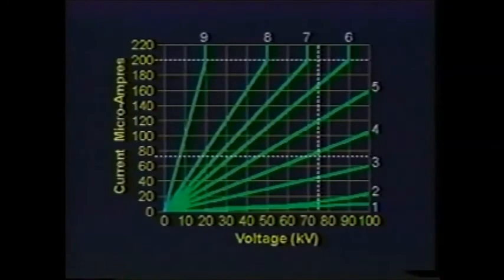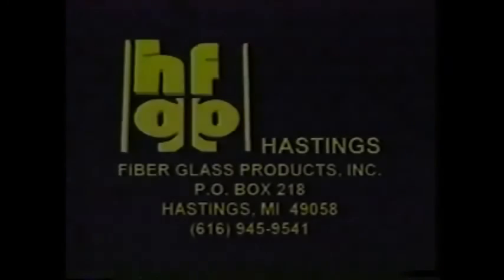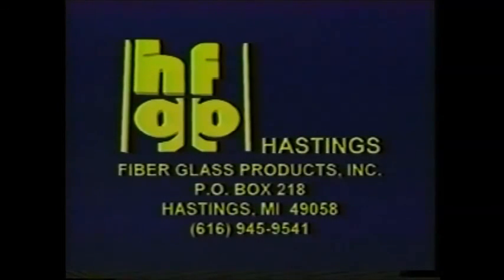This value will vary with the type and extent of contamination. To set 200 microamps as the accept reject level would come as close to approximating OSHA requirements as possible. However there may be situations where an unusually contaminated tool might only measure 180 microamps prior to flashover. Since we are using a reduced voltage and must be sure to always meet or exceed the OSHA requirements we have to set the pass fail requirement of leakage current at 75 microamps. For additional information please contact Hastings Fiberglass Products.